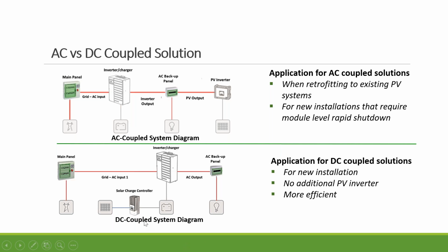In the DC coupled solution, you have a PV array that is all connected to a charge controller, which takes the DC power, does a DC to DC conversion and charges the battery. The battery is also connected, of course, to the hybrid inverter as well. The hybrid inverter will supply power to the backup load panel, as well as connect to the main panel and to the grid. It's more favorable for new installations, because then you do not need an additional PV inverter, and it's more efficient.